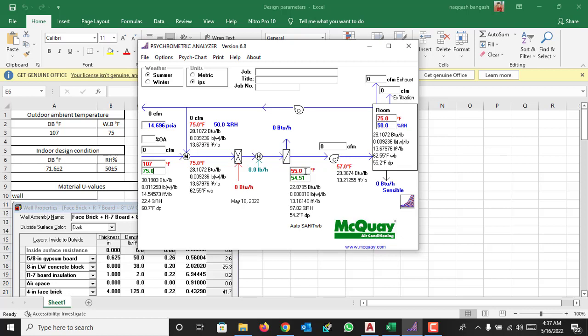Like we consider the supply CFM is 400 and we are going to supply 10% of the supply air as fresh air, so 10% of the supply air is 40 CFM.